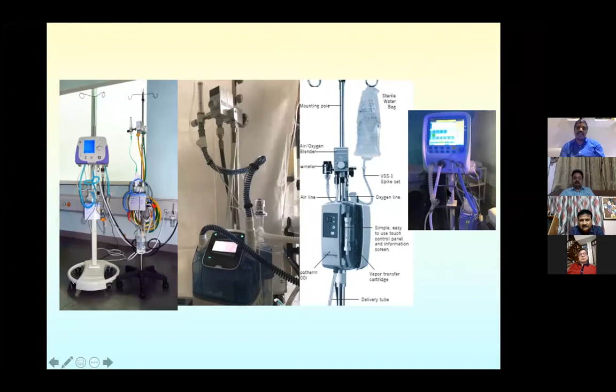These are the different types of humidifiers which are available in the market. The cost range of all of them is the same, somewhere between 80 to 90,000 rupees. But whenever you buy a humidifier, you have to ensure that the display temperature should be 37. That means the gas going to the baby goes at 37 degrees Celsius, and it should have a heating element in the inspiratory limb. So in the inspiratory circuit, there should be a heating wire. And this wire continues to heat the gas from the humidifier till it goes to the patient.